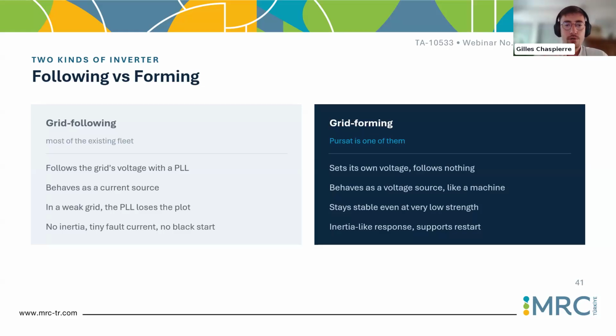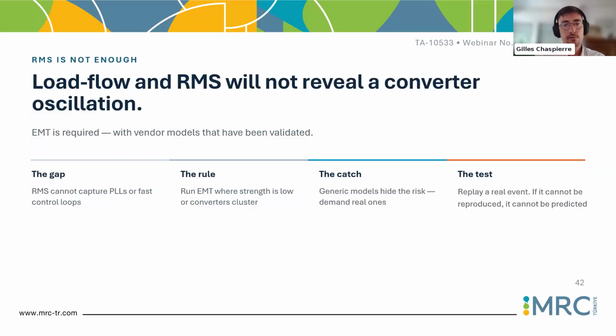And also my last point, a limitation of this grid forming technology is that it's not mature for all technologies. Today, it's mainly mature for batteries, because it relies on an energy reserve to work properly. So batteries are very mature, and it's also recommended to enforce grid forming for batteries in the technical requirements in your own national grid code, to make sure you bring additional robustness to your system while limiting grid reinforcement and hence investment in your grid. Yes, next slide, please.